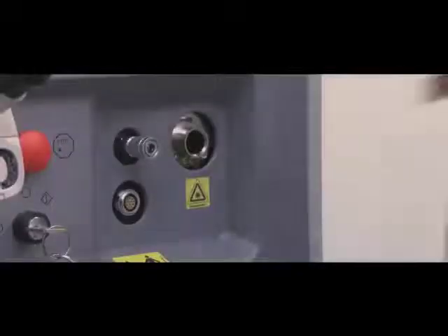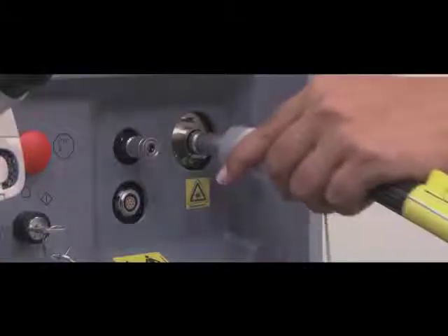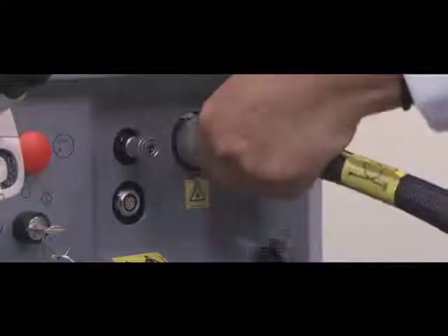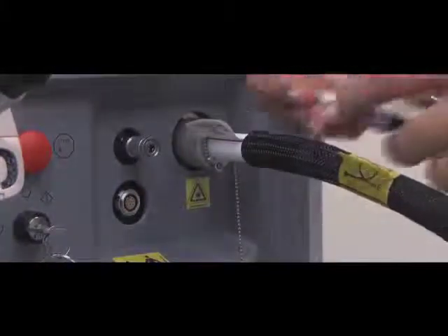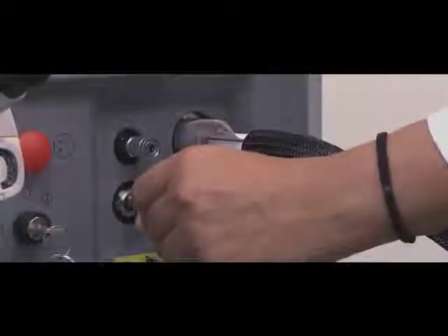The delivery system consists of the electrical cord, the cryogen line, and the optical fiber. It must be handled at all times with extreme care. Make sure the cables are hung and not on the floor. When attaching the delivery system to the device, always attach the optical fiber first, lining it up and pushing.